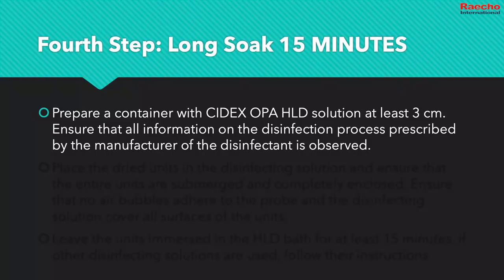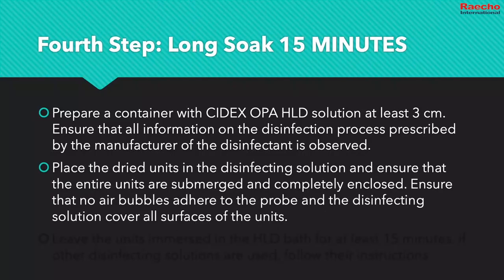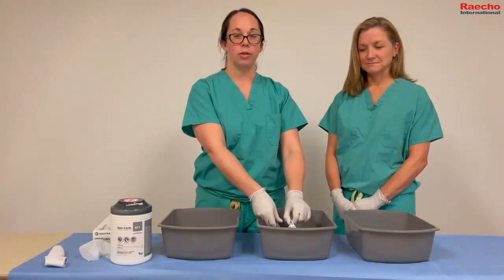Ensure that all the information of the disinfection process prescribed by the manufacturer of the disinfectant used is observed. Place the dried units in the disinfecting solution and ensure that the entire probes are submerged and completely enclosed. Ensure that no air bubbles stick to the probe surface and that the disinfecting solution covers all surfaces.